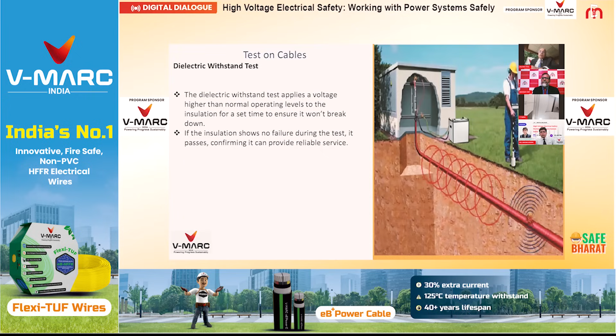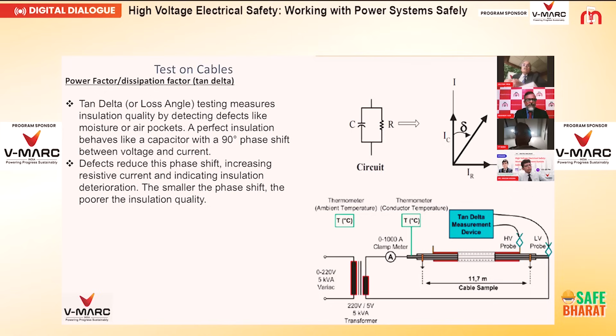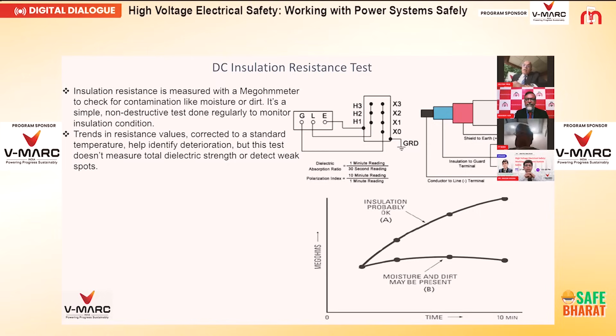Then the next test is basically power factor and dissipation factor test. These are again regular tests to be conducted to check the condition of our circuits and installations. Then the DC insulation resistance test is the next one, which gives you the proper condition of the core, how it is present in critical situations, and how it is performing underground. This gives you a clear indication on the test.